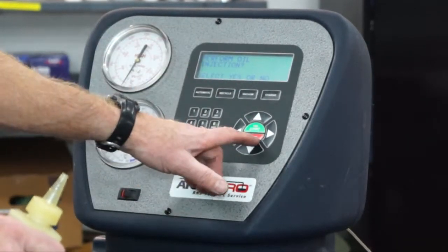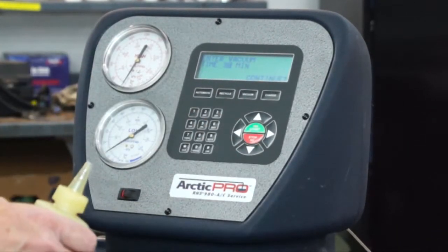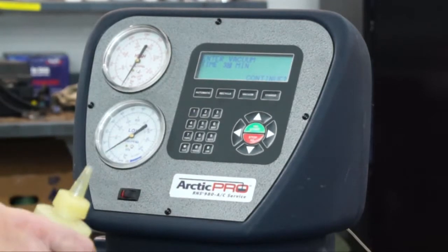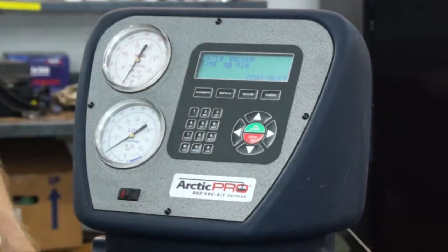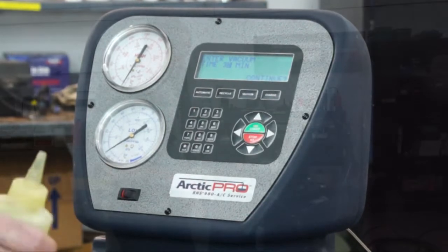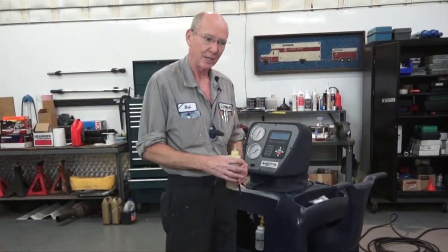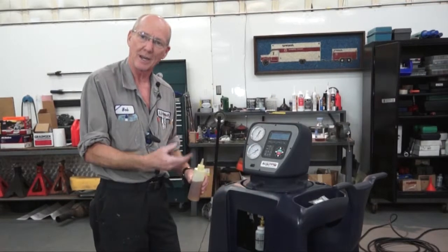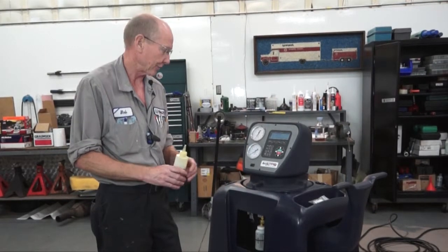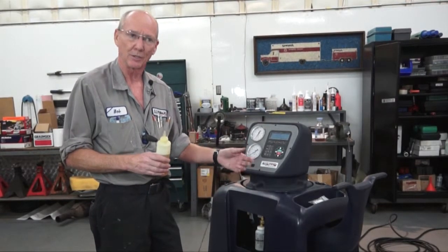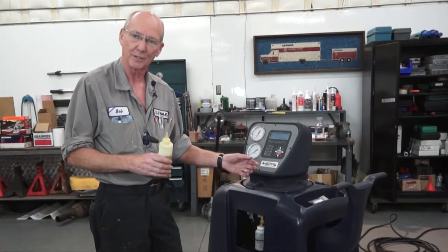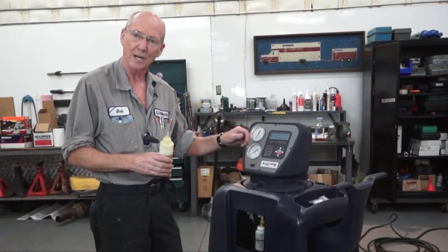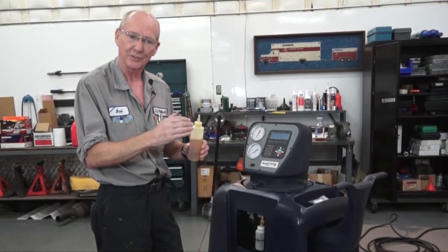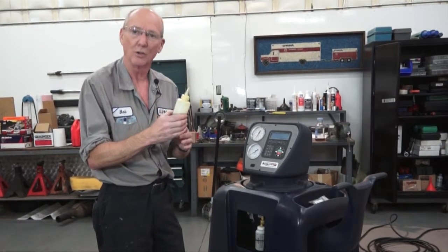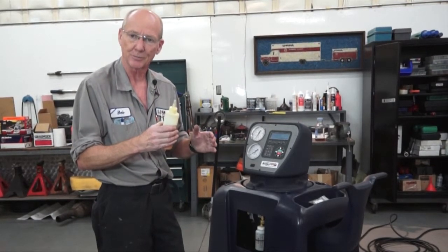It's going to ask me to perform an oil injection. Of course, no. It's going to ask me to enter the time of vacuum. Mine defaults to 30 minutes, so I'm just going to leave it there. It doesn't matter at this point. What I'm trying to do is take the oil that's in there and run it through the vacuum pump. As it's running, I'm going to leave the cap on for 2 minutes. After 2 minutes, I'm going to pull the cap off, and while I'm looking at the sight glass, I'm going to pour the remainder of the oil in the vacuum pump so it disperses properly.